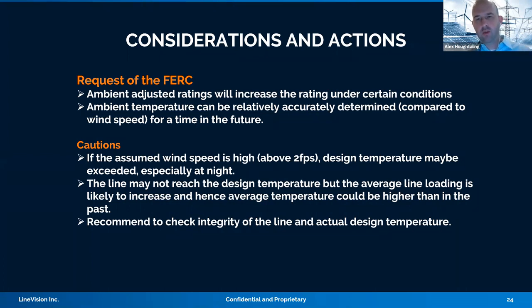Secondly, thinking about the mandate for ambient adjusted ratings, we have the ability to incorporate ambient adjusted ratings with weather validation, like Rob was saying - wind is the most crucial aspect, so incorporating that is important. And then, to Rob's point about understanding the current state of your conductors and the aging process, and what that might mean for potential clearance violations or thermal capacity, another application of ours called Line Health allows us to assess the overall health of your conductor.